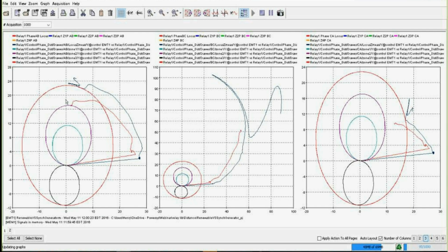now the relay sees something completely different, because the inverter tried to balance the fault, to inject a lot of positive and negative sequence. The trouble we have here is that in one case we were outside of the zones, but with the wind park, which produced the same amount of power, we now get inside the zone too. That's a concern, because now we can trip a relay that is not supposed to trip. So it's a pretty big concern.